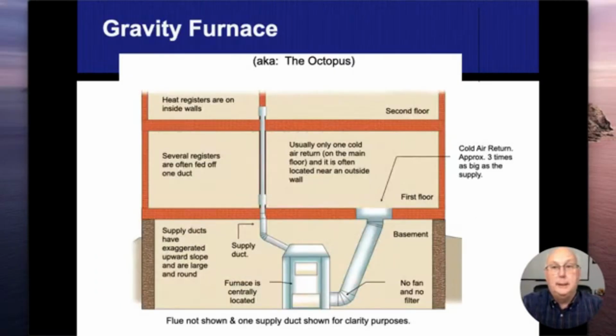All right, we're going to start getting into our different types of furnaces. The first one you're expected to recognize is called a gravity furnace. Gravity furnaces did nothing but turn a fire on and turn a fire off. The heat exchangers of these things were thick cast iron. I want to say probably about 1.5 inches to 2 inches thick, maybe even 3 inches. They were just big and solid, all right?